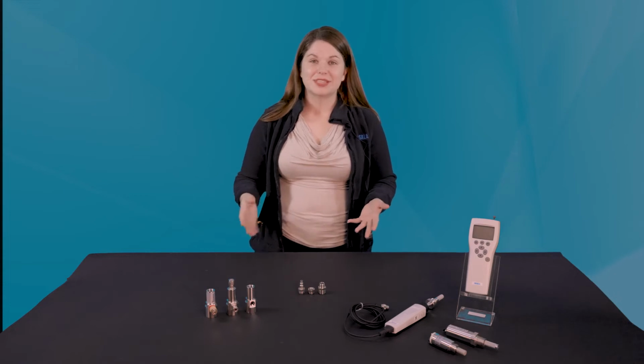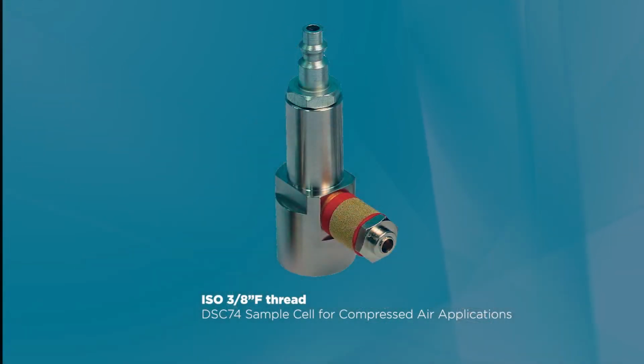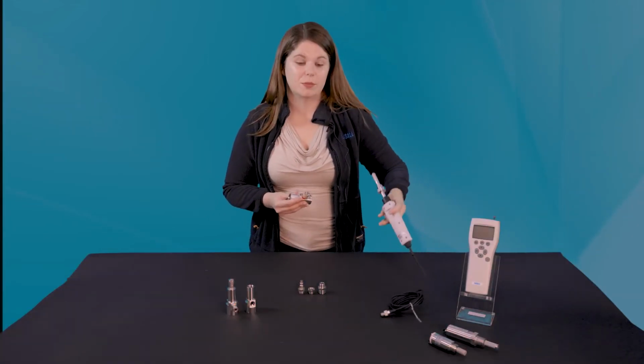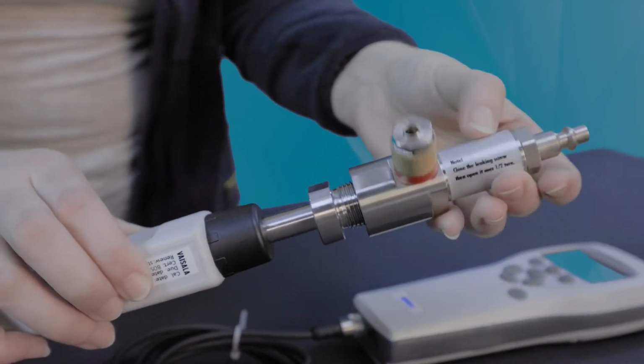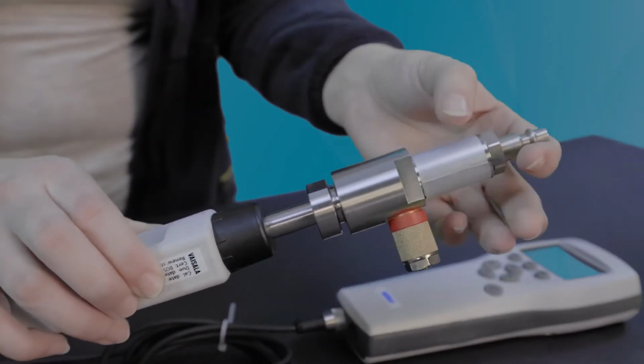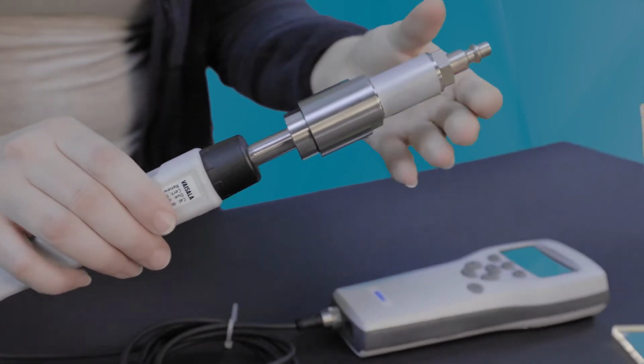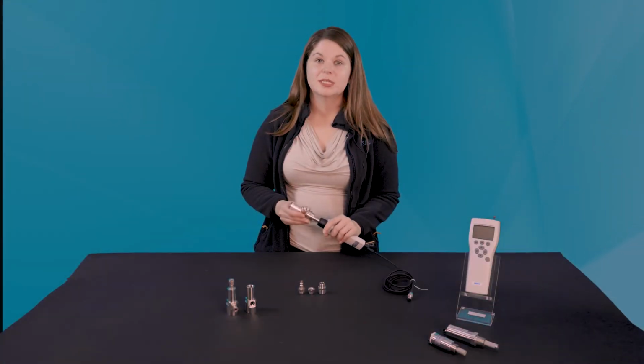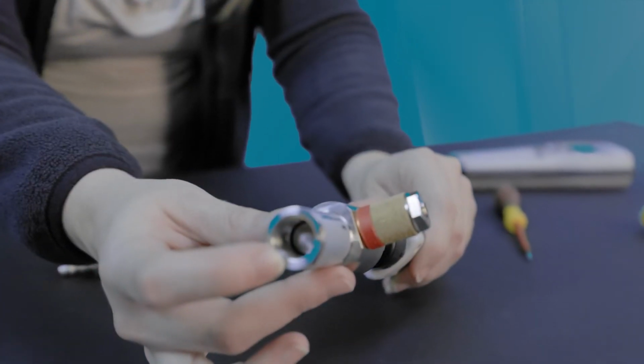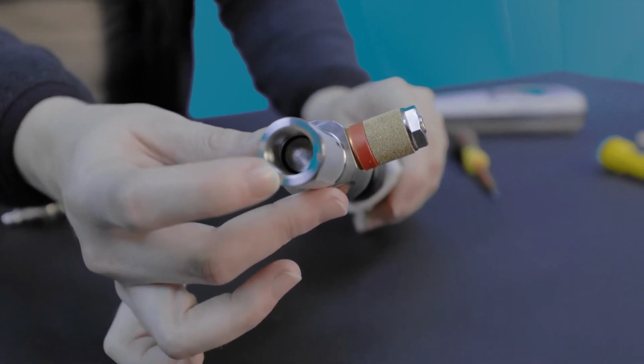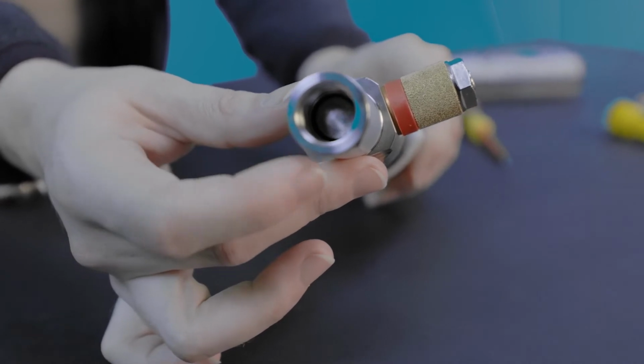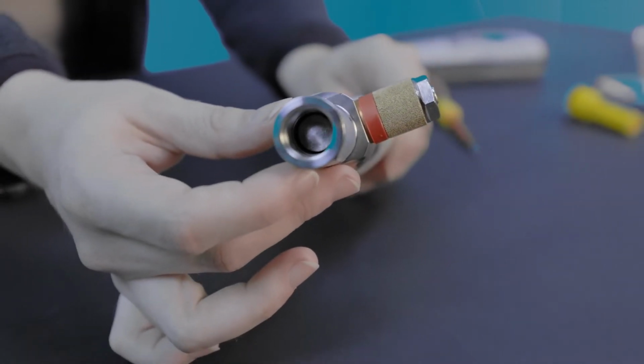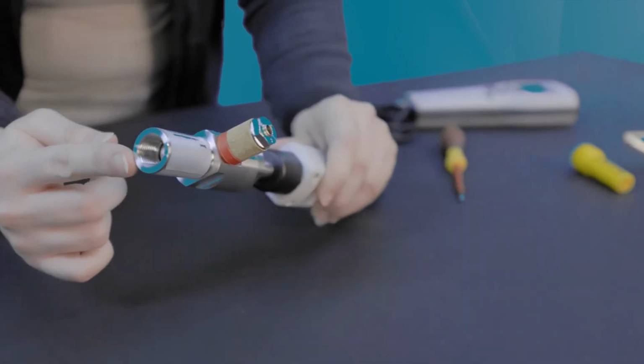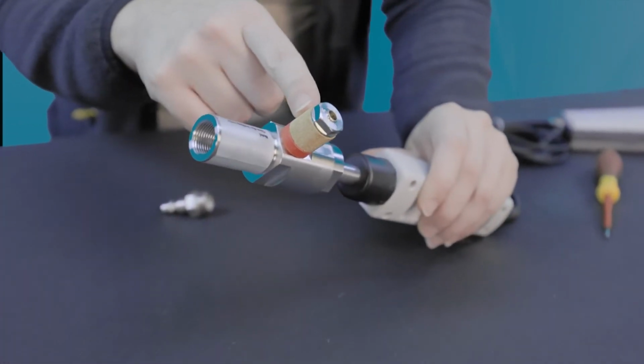Our most used sample cell is the DSC74, which is specifically designed for compressed air applications. I'll install this onto a DMT242 probe for demonstration. Once installed, the process connection between the probe and sample cell is pressure tight up to 10 bar. If you look here, you can see that the probe tip takes up most of the space in the sample cell chamber. There's a threaded inlet at the top of the sample cell and a leak screw on the side.